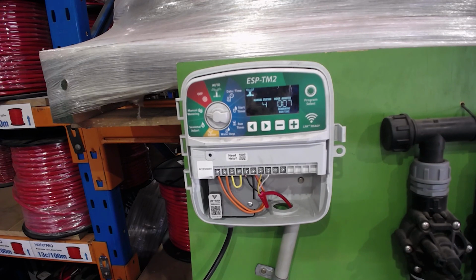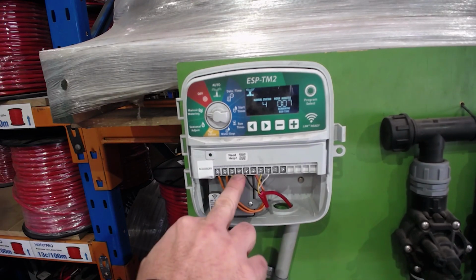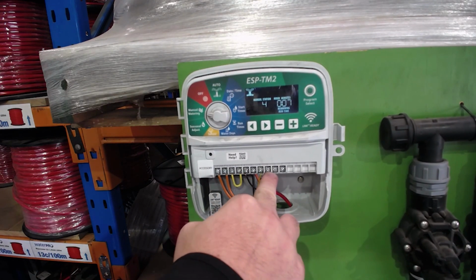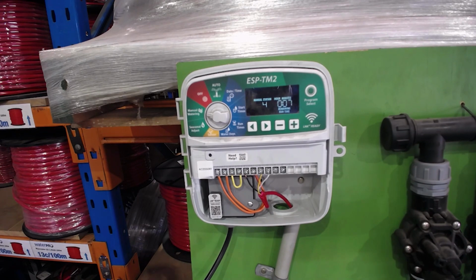Take that coil out, look across your valves, across the 2 wires. You might see black and red here, which means you'd go into that valve box and see the red cable in that solenoid, and you would grab the red cable and the black cable and test the voltage. You might see 11 volts, 12 volts, which is a really low amount of voltage, which means there's either nicks in the cable because you're losing voltage out through them, and that tends to happen at times like this in the year where it's wet, because water's a conductor, so it'll want to go out a lot easier.